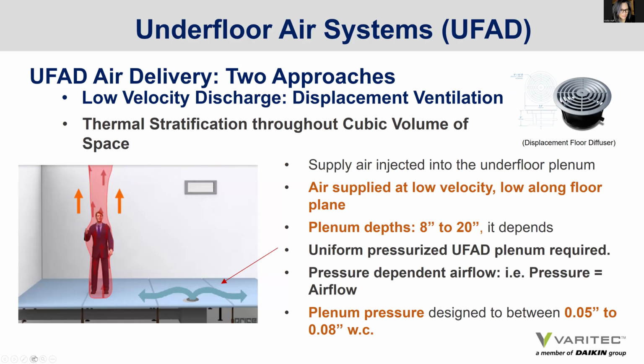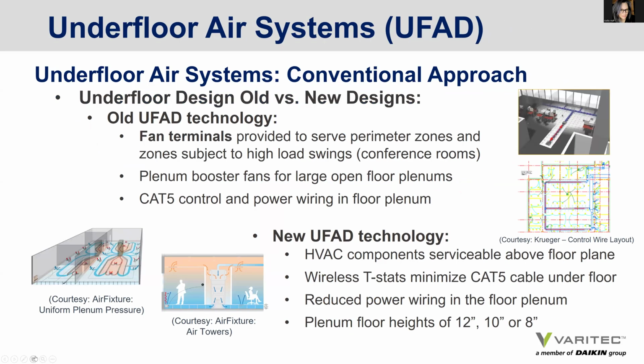So what's exciting about underfloor air is that it's a technology that continues to evolve. In the past, fan terminal units were required to condition perimeter zones, areas with high load swings such as conference rooms, and those terminals were of a certain height, about 14 inches, that often required floor plenum heights to be 16 inches or taller in a space. So a lot more room was required. Sometimes in very large open floor plenums, booster fans were required. And also other mechanical items were necessary, such as power transformers, power wiring, Cat5 control wiring for VAV applications, etc.